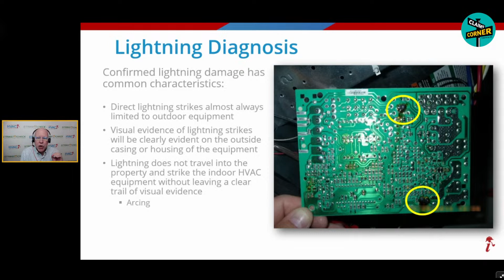So if you see arcing marks, and multiple arcing marks, especially on multiple components, that's a pretty good indicator if you're trying to diagnose lightning. Then we have this very unique signature here called ghosting. Not everybody has seen this, but this is very specific, and you almost always know you're looking at lightning if you see ghosting. Let me explain what's happening here. We have a piece of EMT, electrical metallic tubing, which is conduit. It's metal. It's got wires in it: a white wire, yellow wire, orange wire. I wish we had opened this up and shown you. The lightning wasn't traveling in the wires. The lightning was physically traveling through the metal conduit.